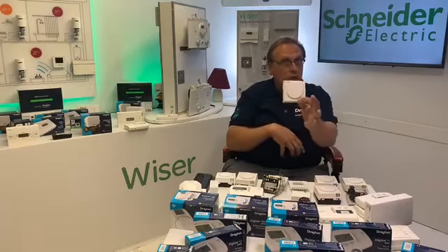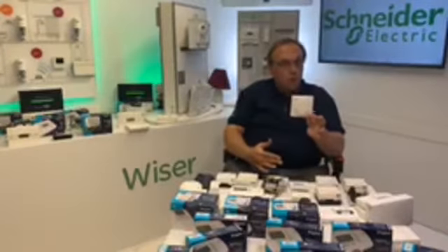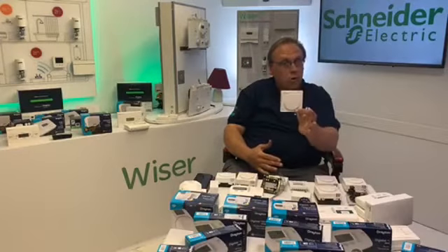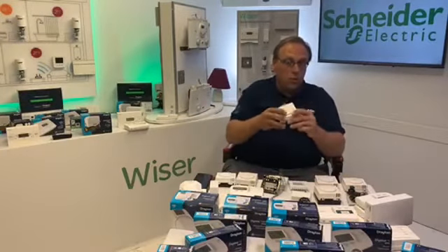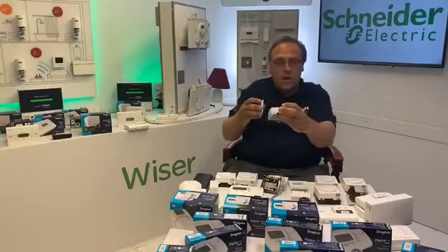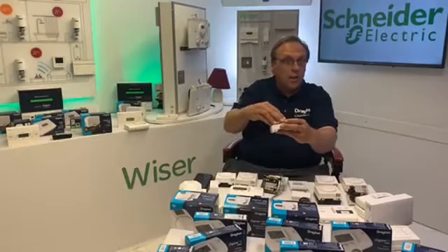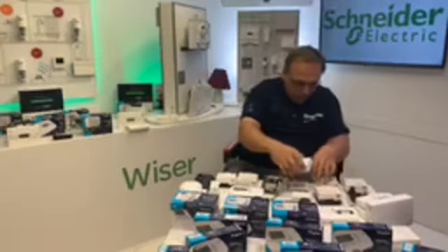So this would be designated as a 4-wire thermostat. Everything we've seen up to now is a 3-wire, but does require a neutral, requires a permanent live, and then you've got your switching contacts throughout. But in terms of range limiting, exactly the same under the cover, exactly the same swing on temperature, 10 to 30 degrees. So RTS4 is volt free.